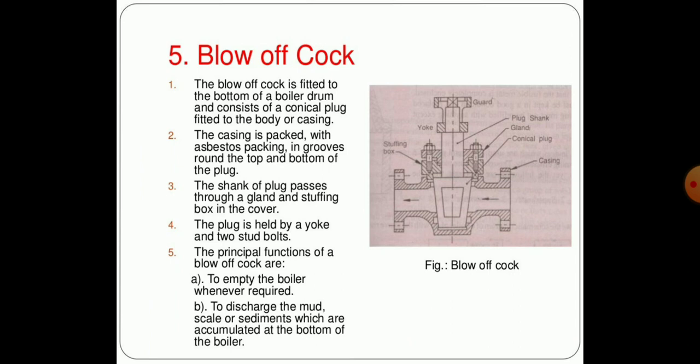Another one is blow off cock. The blow off cock is fitted to the bottom of the boiler and consists of a conical plug which is fitted to the body or casing. The casing is packed with asbestos packing which goes around the top and bottom of the plug. The shank of the plug passes through the gland and stuffing box in the cover. The plug is held by a yoke and two stud bolts. The principal functions of the blow off cock are to empty the boiler whenever required and to discharge the mud, scale, or sediments which accumulate at the bottom of the boiler.